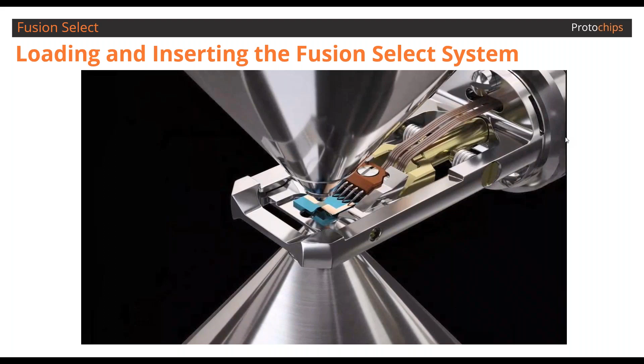And it's important to note that the Protochips system and Protochips holder are designed to fit even very narrow pole pieces, even narrow gaps in pole pieces, while leaving you some room to perform tilting as well, which provides additional flexibility when working on such equipment. Once in the TEM, you can perform tilting in both directions with a friction-free design that ensures that the heating or the electrical stimulation that you send is crystal clear and not disturbed by the tilting mechanism. And the full idea behind that design is that you can access all of the tools that you have in your microscope, from the tilting to the EDS detectors as shown here, EELS, TPC. You don't have to limit yourself in any way when doing an in situ TEM experiment. You can still benefit from the full capabilities of your TEM.